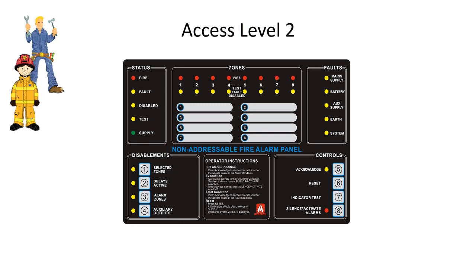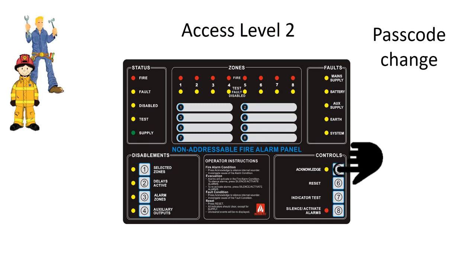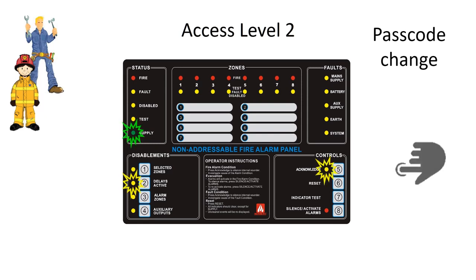To change the Access Level 2 passcode, place the panel into Access Level 3 and press the Acknowledge button for 10 seconds. The supply LED will flash rapidly. Press the 2 button for Access Level 2. The Acknowledge LED and the Delays Active LED will both flash. Press the Acknowledge button to confirm and the Acknowledge LED will be off. At the same time, the Delays Active LED will be on.